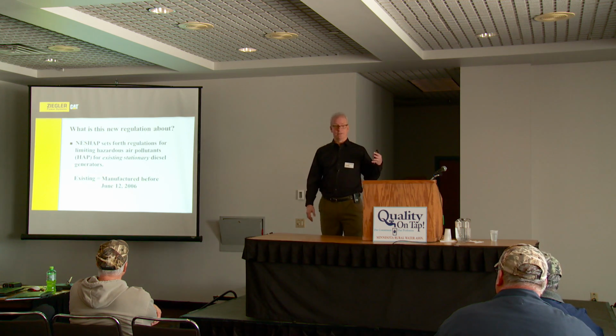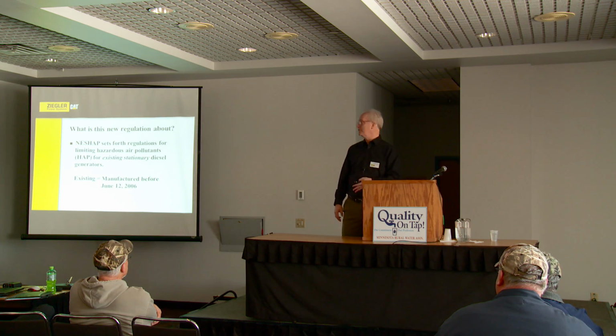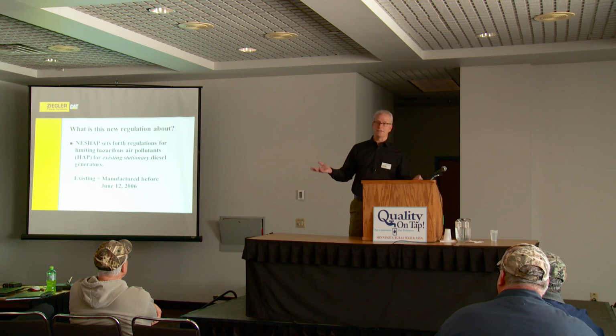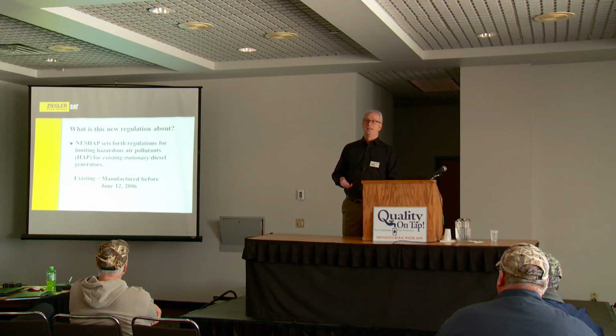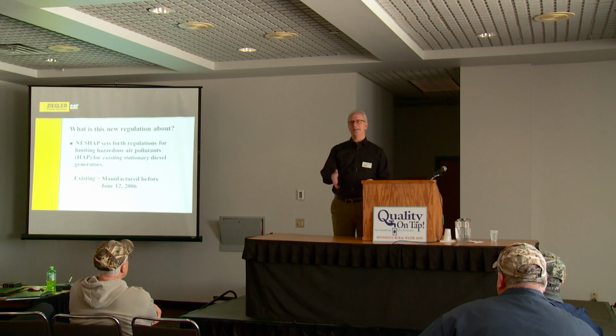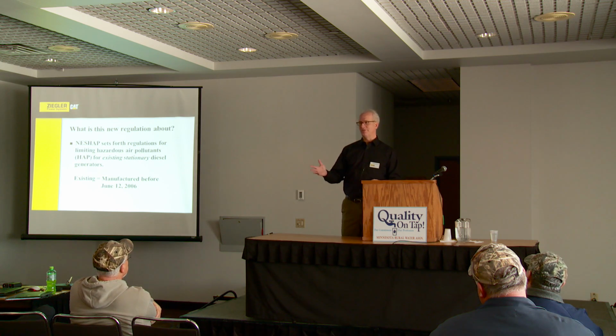So, as I said before, the regulation is looking to reduce hazardous air pollutants, primarily formaldehyde, and it's trying to do that for existing stationary engines. So what's an existing engine? Well, the rule makes it really simple. It's an engine that was manufactured before June 12, 2006. And it almost correlates with when these tier rules started to happen, when they started making engines tier 1 and tier 2. They're saying, if you've got a new engine that's been regulated under the new source performance standard, you don't have to do this thing for NESHAP.